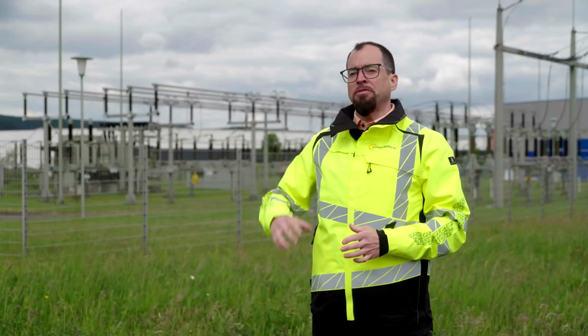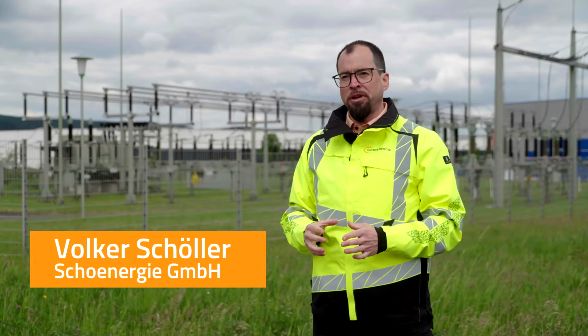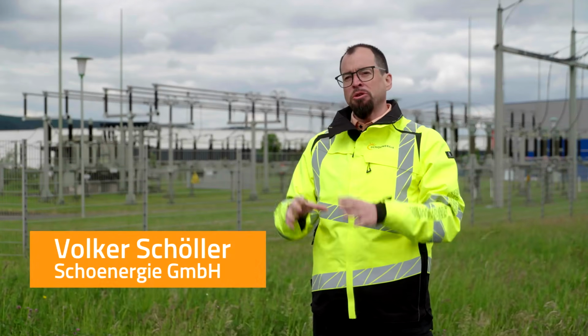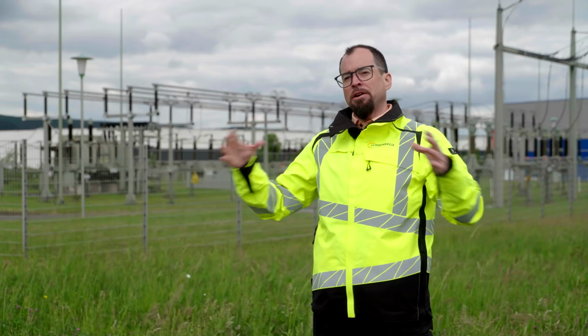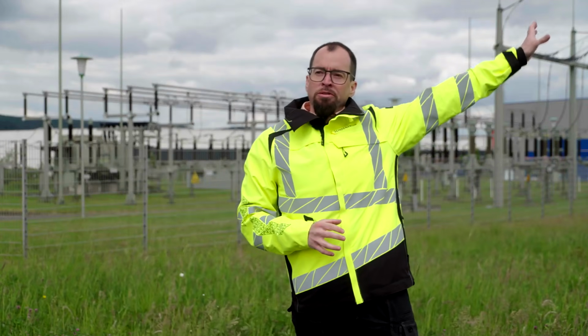We would be able to restart the system much faster after a blackout and create a much more resilient grid. We would have 4,000 points that restart on their own and then resynchronize with the 110 kilovolt grid, which are the transmission lines we have here, and then reconnect to the grid.